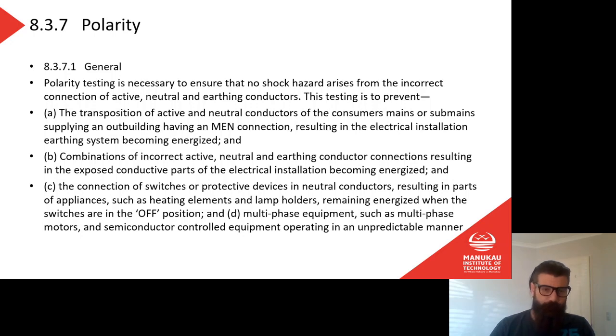And the third one: the connection of switches or protective devices in neutral current conductors, resulting in parts of an appliance such as heating elements or lamp holders remaining energized when the switches are in the off position, and multi-phase equipment such as multi-phase motors and semiconductor controlled equipment operating in an unpredictable manner.